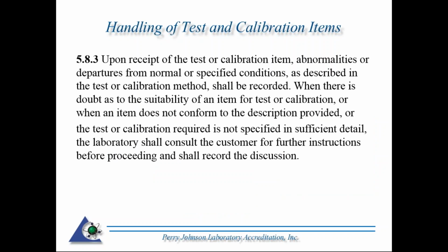Okay, 5.8.3, clause number 3. Upon receipt of the test or calibration items, abnormalities or departures from normal or specified conditions as described in the test or calibration method shall be recorded. When there is doubt as to the suitability of an item for test or calibration, or when an item does not conform to the description provided, or the test or calibration required is not specified in sufficient detail, the laboratory shall consult the customer for further instructions before proceeding and shall record the discussion. Okay, so I'm going to leave that up for a few moments and we'll dissect this a little bit.